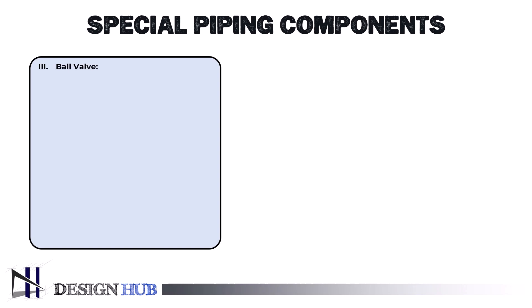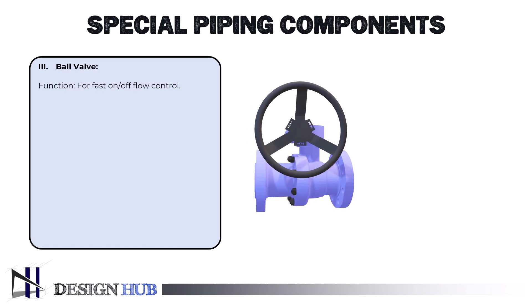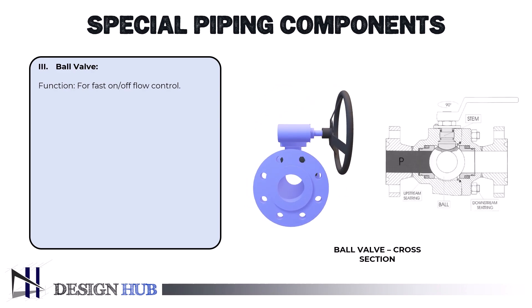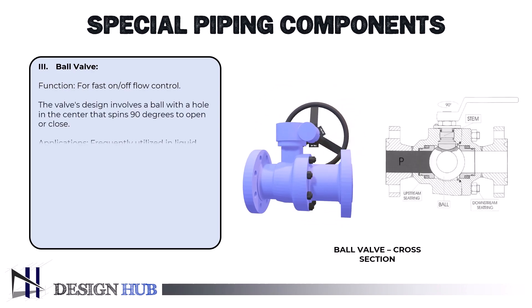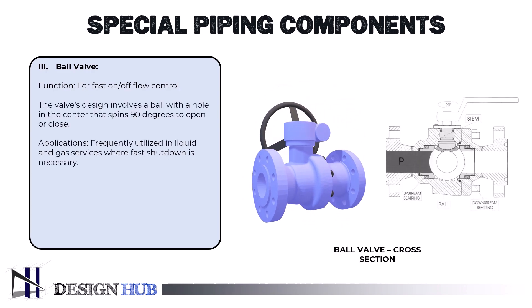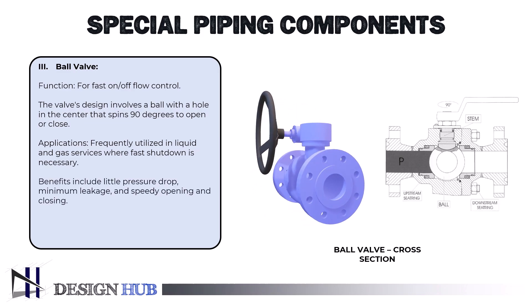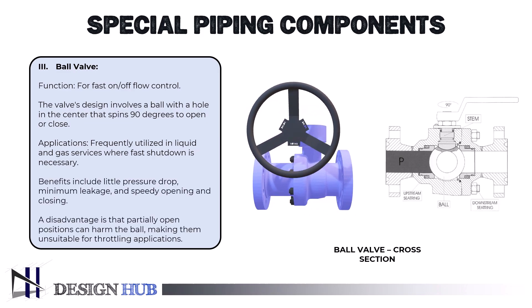Now, let's see what a ball valve is. A ball valve is a flow control device that regulates fluid flow by pivoting a hollow, perforated ball. It is open when the hole through the center of the ball is parallel to the flow inlet, and closed when the valve handle is turned 90 degrees, preventing flow. When open, the handle is flat and aligned with the flow, and when closed, it is perpendicular to it, allowing for easy visual confirmation of the valve's status. The shut position could be one-quarter turn clockwise or counterclockwise.